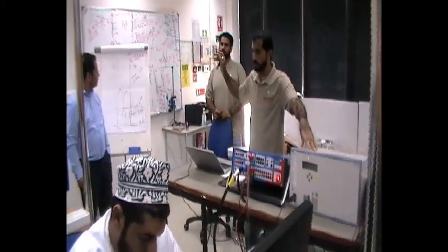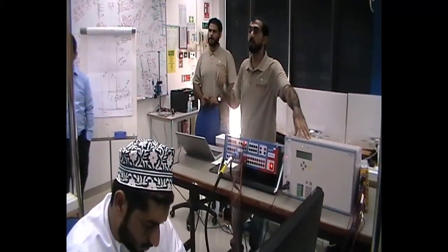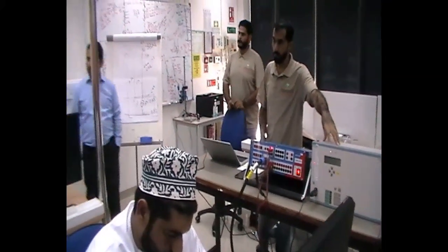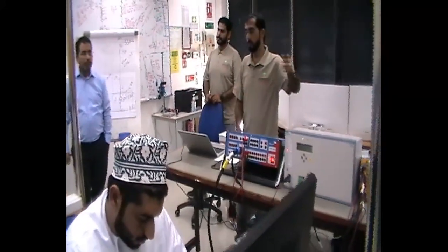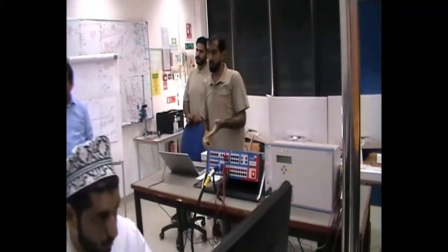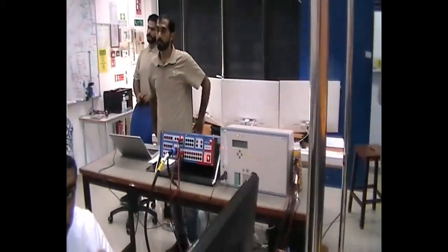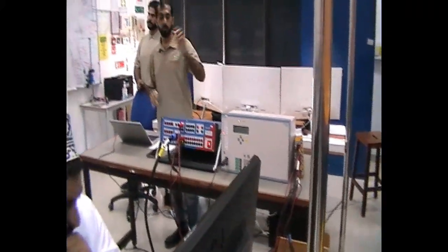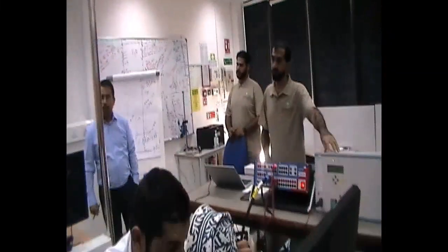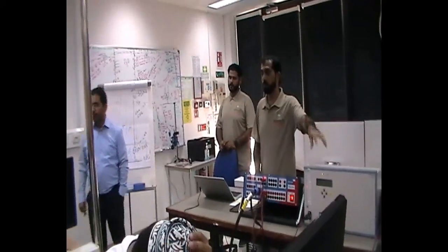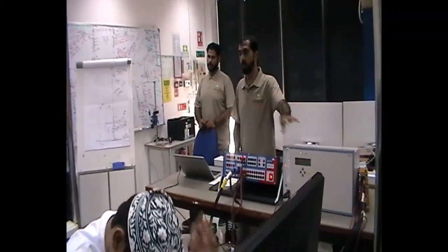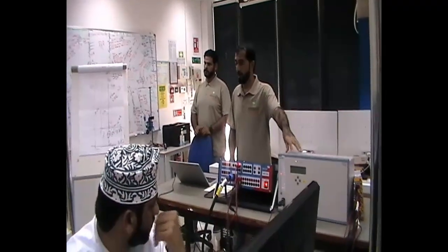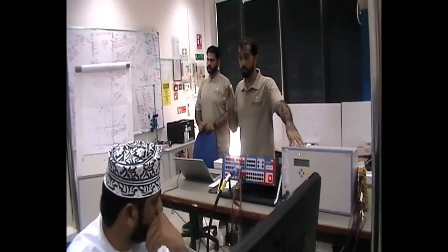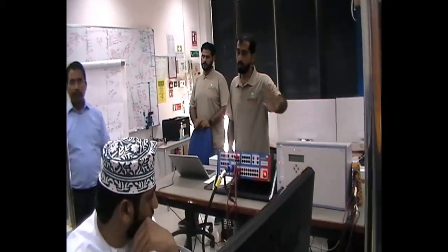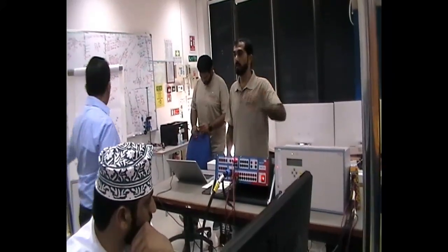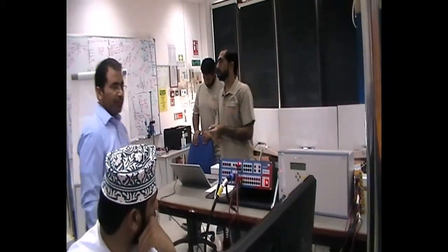If the fault is in the line, it will trip in 0 seconds because it will see it in zone 1. So whatever you put in the setting, it will act based on it. But you can cover whatever you want at the same time. Everything you do is during setting. Setting is very, very important. Once you've done your setting, if it operated wrong, mostly it will be because of the setting, not the relay. Relay maloperation is very, very rare. Yes, please.